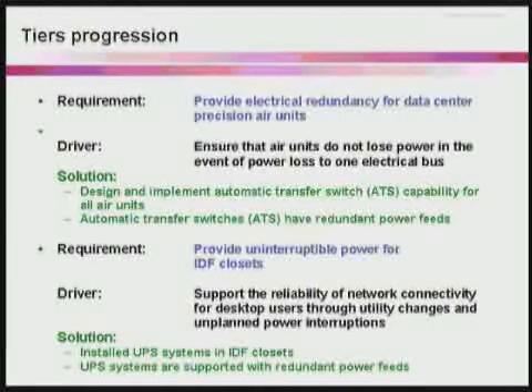To ensure that the computer room air conditioners did not lose power in the event of a power loss of one of the critical buses, electrical redundancy was added to the computer room air conditioners. They were mounted post-transfer switch, so the automatic transfer switches would provide protected power to the computer room air conditioners in the event of a power loss. Finally, they wanted to add uninterruptible power to the IDF closets. In this case, they installed UPS systems in the IDF closets, and they were supported from redundant power feeds.